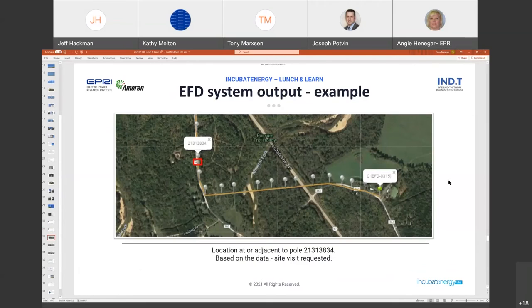Thanks, Tony, I appreciate the explanation. The point I wanted to make about that last slide is that once we installed these things, we immediately saw activity both on the transmission circuits and on the distribution. In some cases, the transmission stuff didn't rise to the level where we inspected and found a particular thing right off the bat. But certainly on the distribution, as Tony mentioned, we found something exciting right away. This is just a different presentation of that same 34 kV circuit, and we did put sensors on distribution, but that wasn't as interesting as these other cases. What's notable about this section is that it's got a couple taps in the subtransmission circuit, and it has underbuild, and the underbuild even has transformers and secondaries.